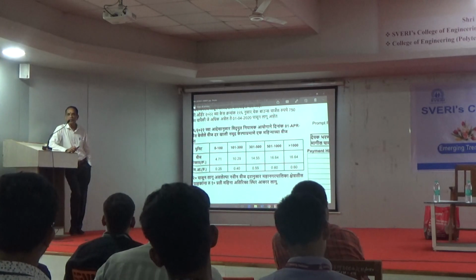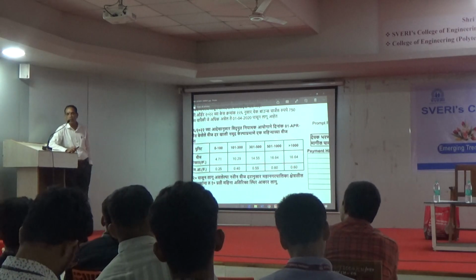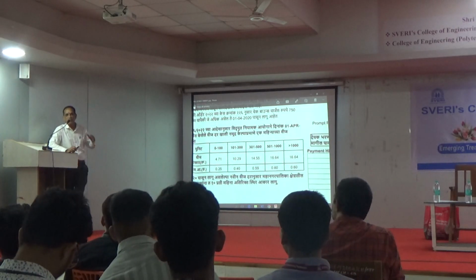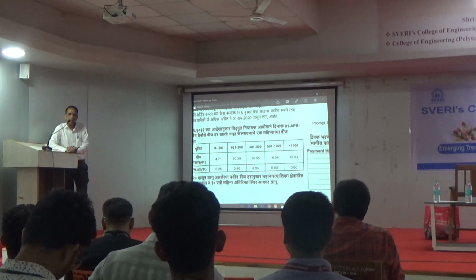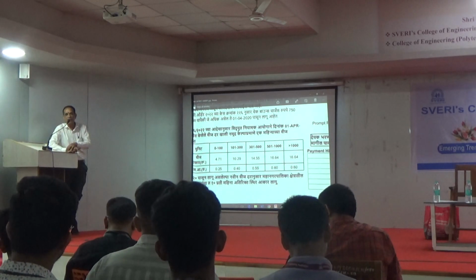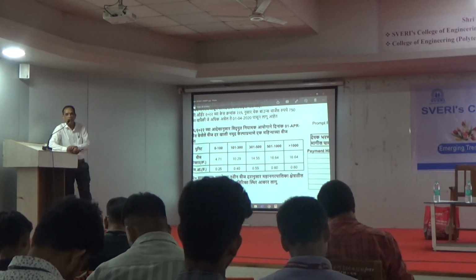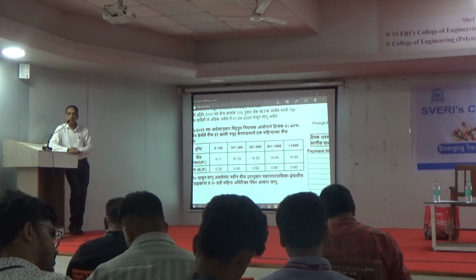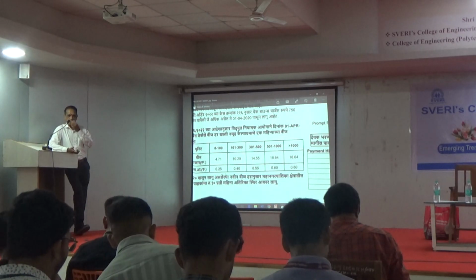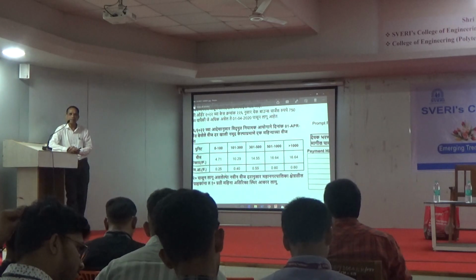So you check all the load components, whether your motor or your fridge. You go for the audit of this load properly, and once you go, say a 1 kilowatt system installed on any roof will generate 4 units per day. Write it down: 4 units per day for a 1 kilowatt system. Generally 5 units are generated, but we take the minimum of 4 units per day per kilowatt. So if your consumption is around 100 units, 1 kilowatt is the ideal system.